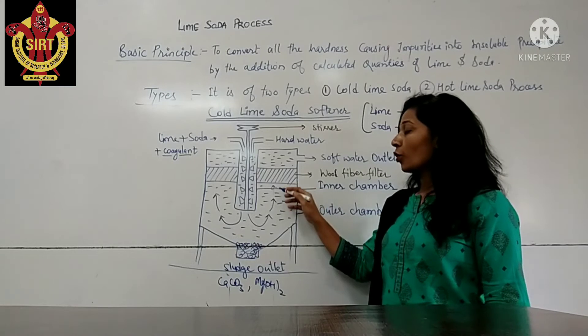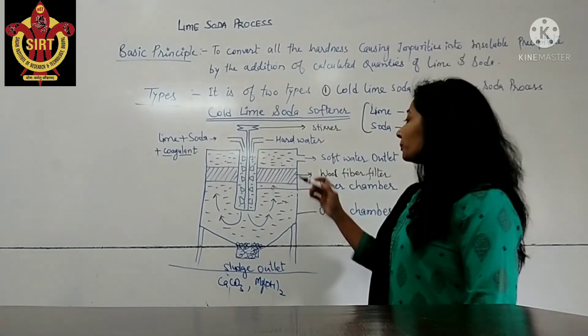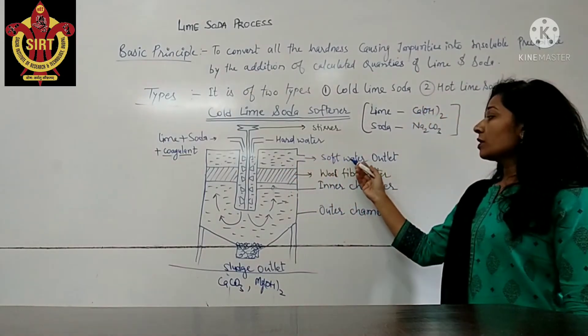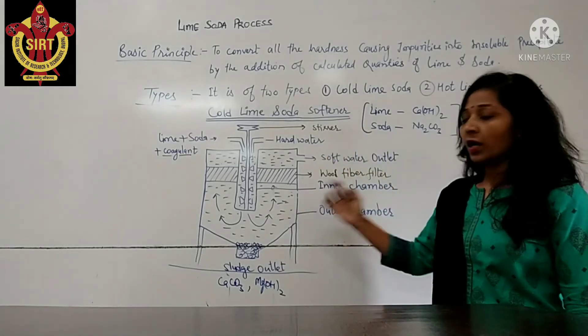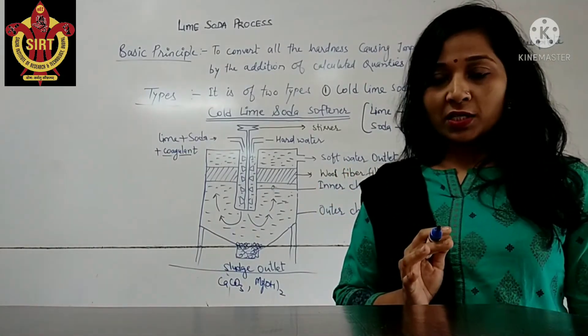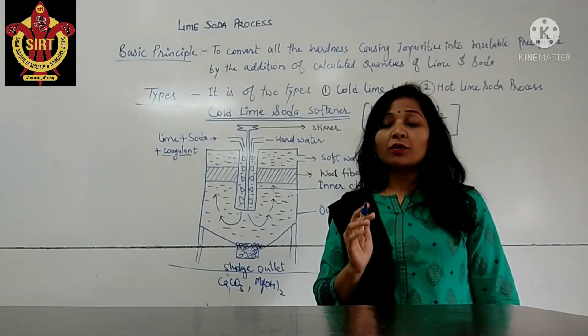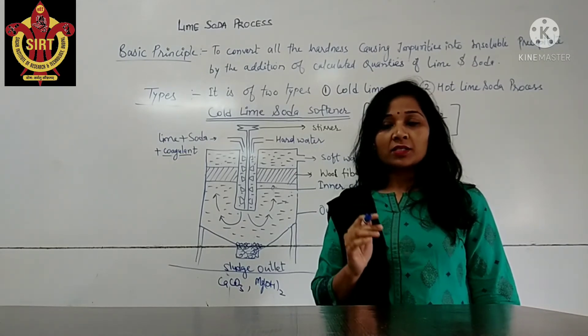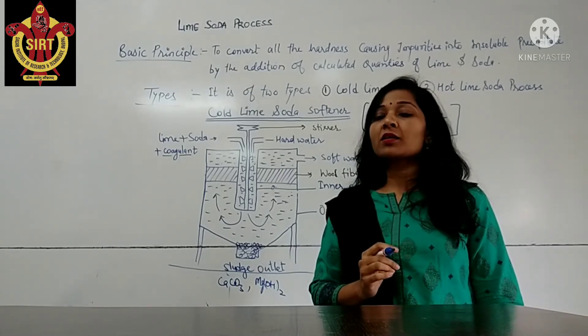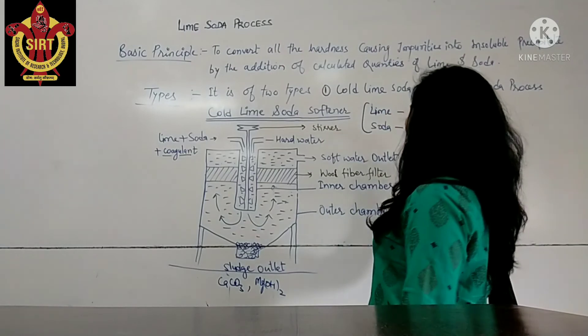After passing through the wood fiber filter, we ensure complete removal of the sludge and suspended matters. In the upper part, softened water is collected and taken out from the soft water outlet. One important point is that after completion of this process, the water obtained has a residual hardness of 50 to 60 ppm. That is a remarkable point — the residual hardness of the converted soft water after this process is 50 to 60 ppm.